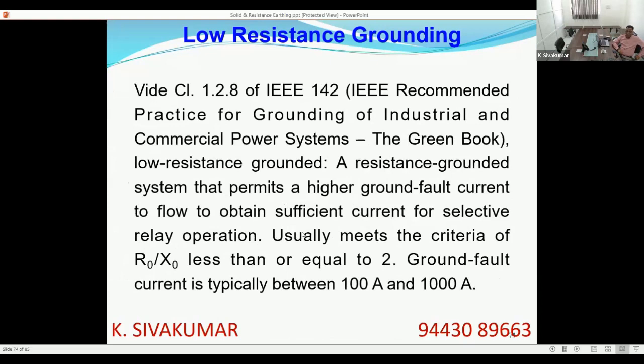In the IEEE Green Book, again there is a definition for a low resistance grounded system. It permits a higher ground fault current to flow to obtain sufficient current for selective relay operation. It usually meets the criteria that the ratio of zero sequence resistance R0 to zero sequence reactance X0 is less than or equal to 2. Ground fault current generally is between 100 ampere and 1000 ampere. This is the definition given in the Green Book.